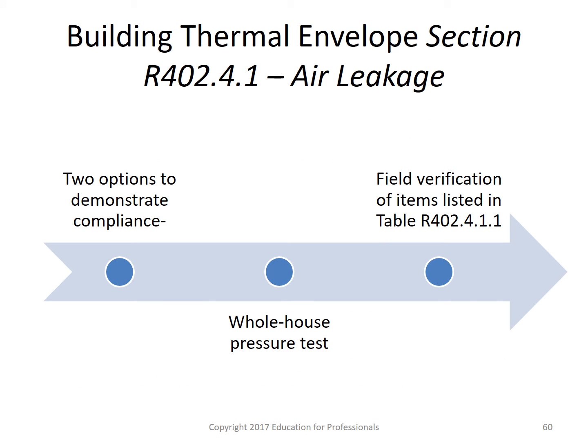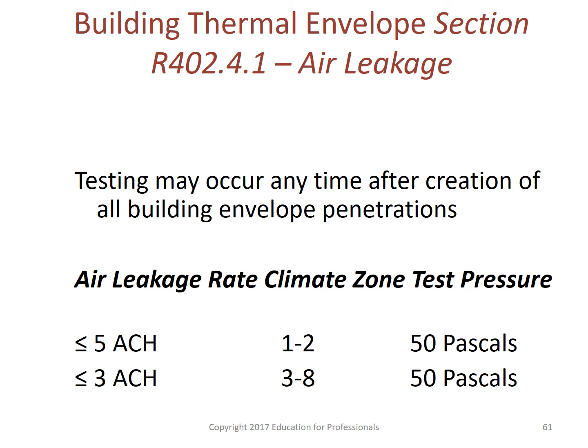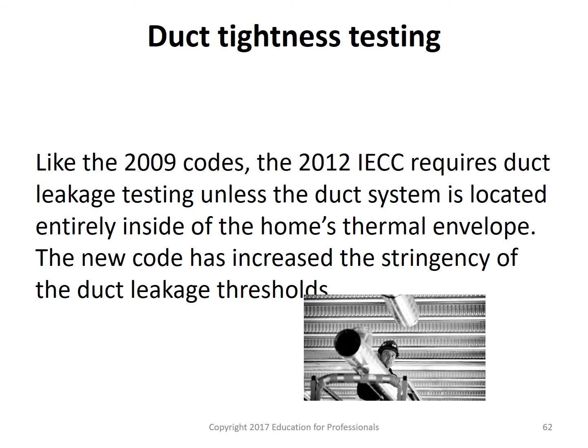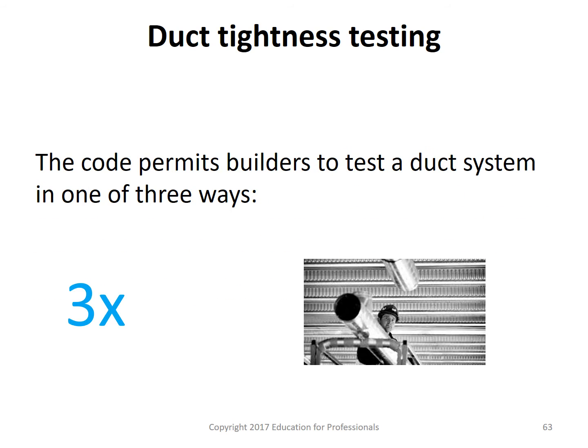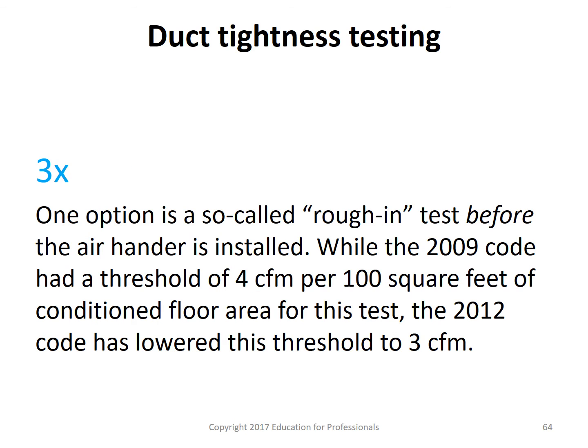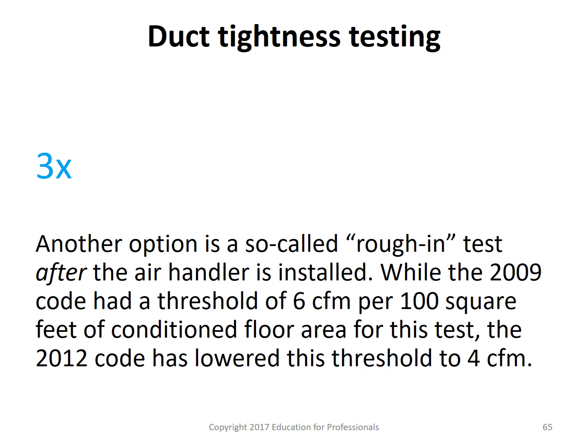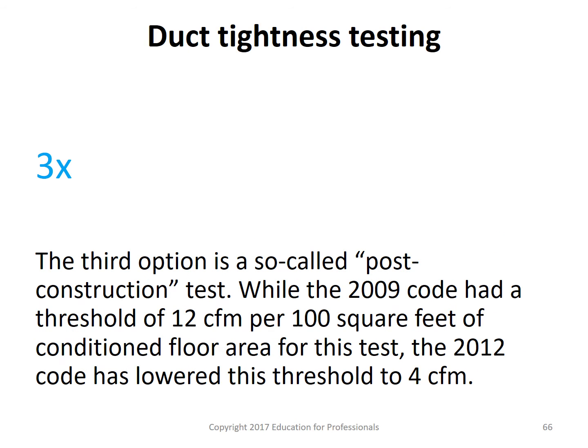Next, we'll take a look at some items on air leakage. Here we'll take a look at some of the air exchange rates, leakage rates per climate zone. And here we'll look at duct tightness testing. The code permits builders to test a duct system in one of 3 ways. One option is the rough-in type. Another option is a so-called rough-in test after the air handler is installed. And a final third option is called post-construction test.